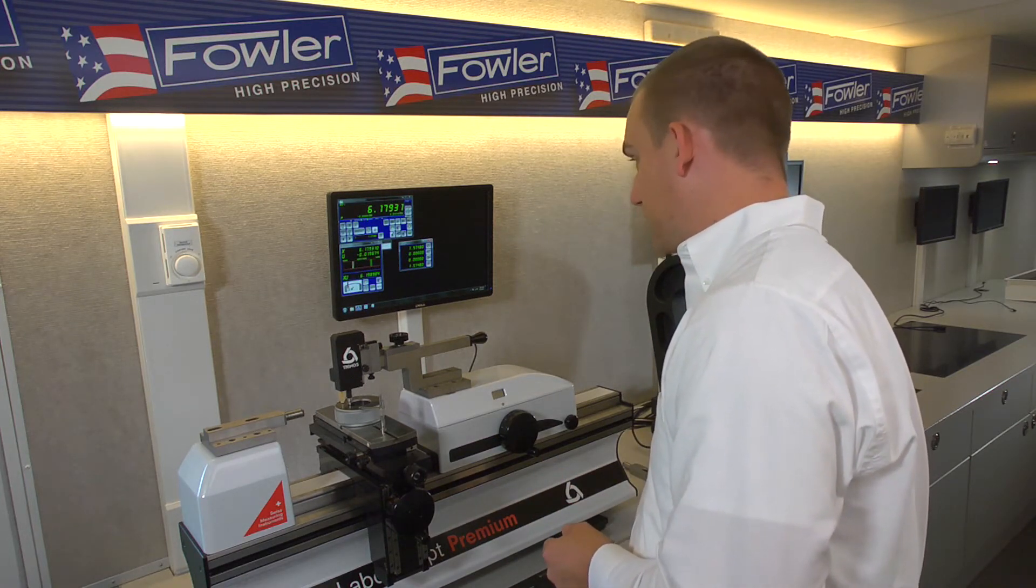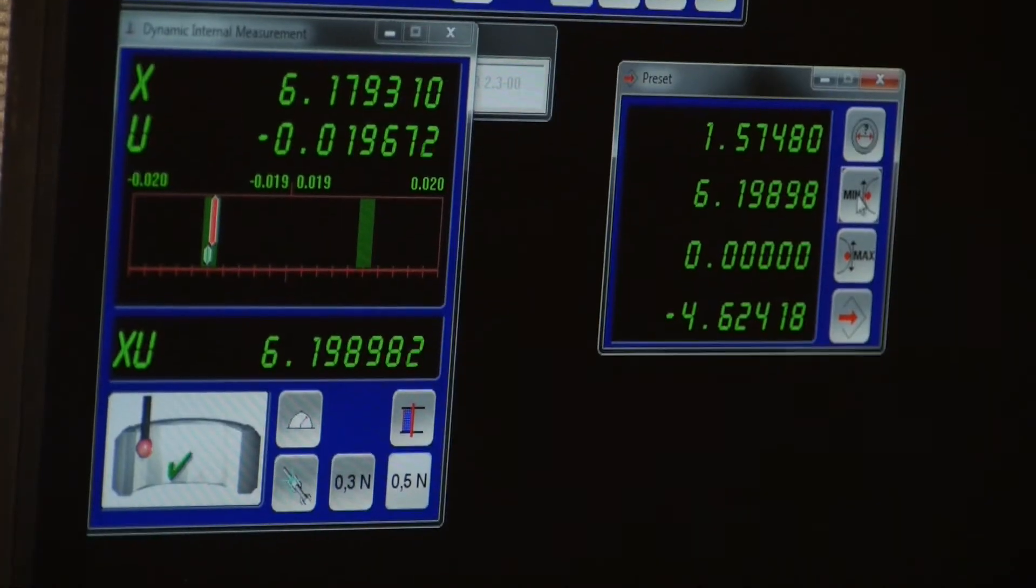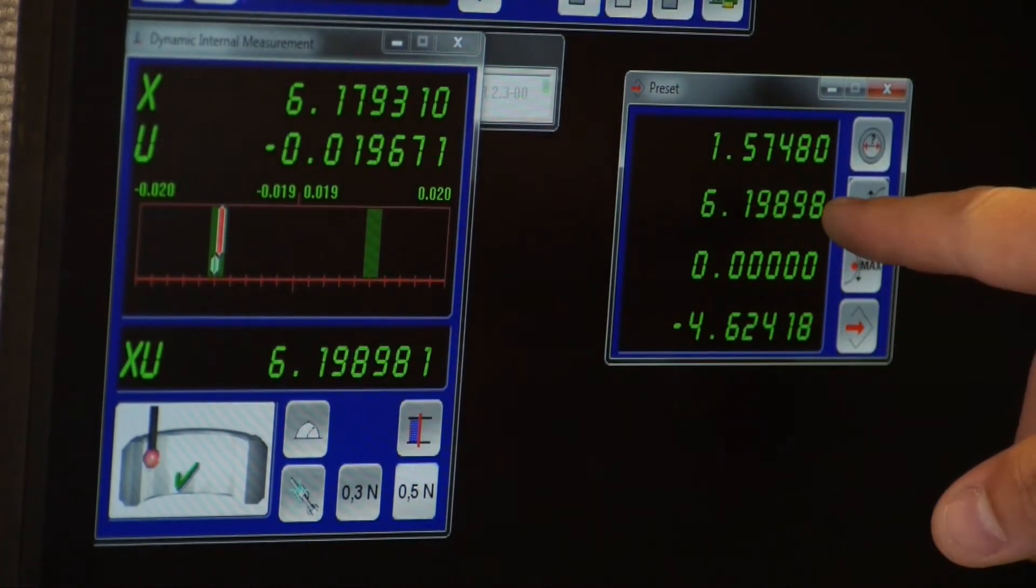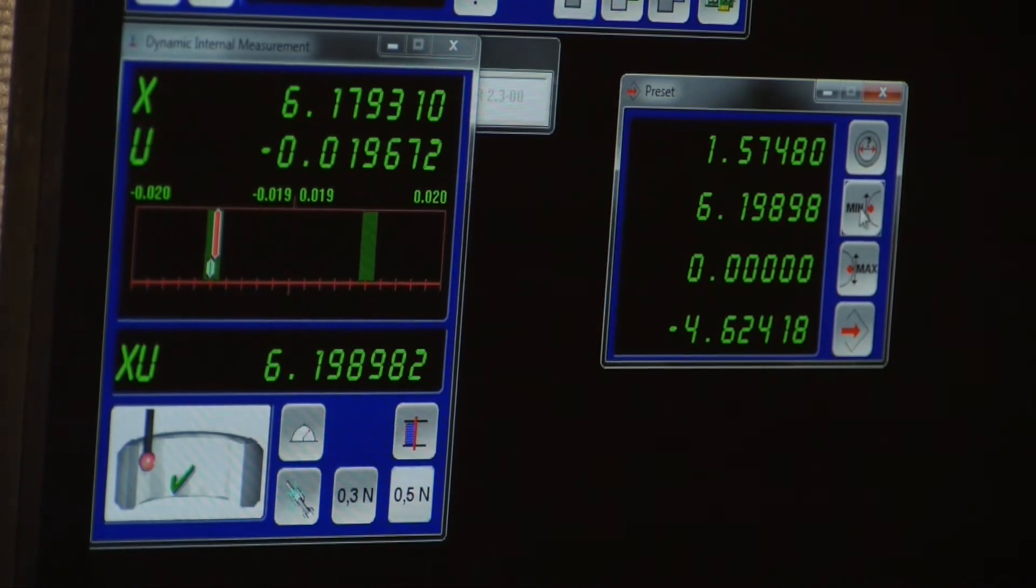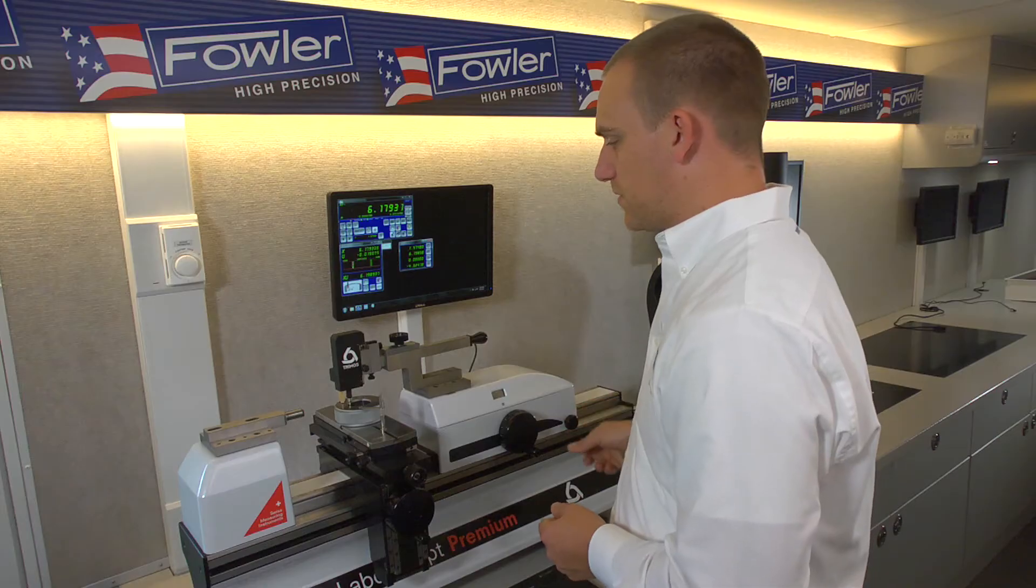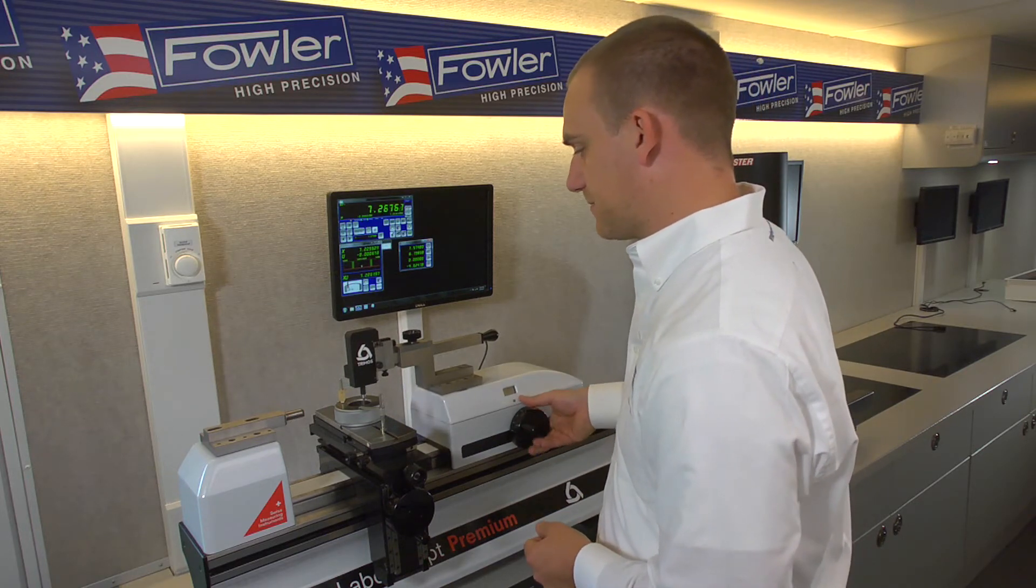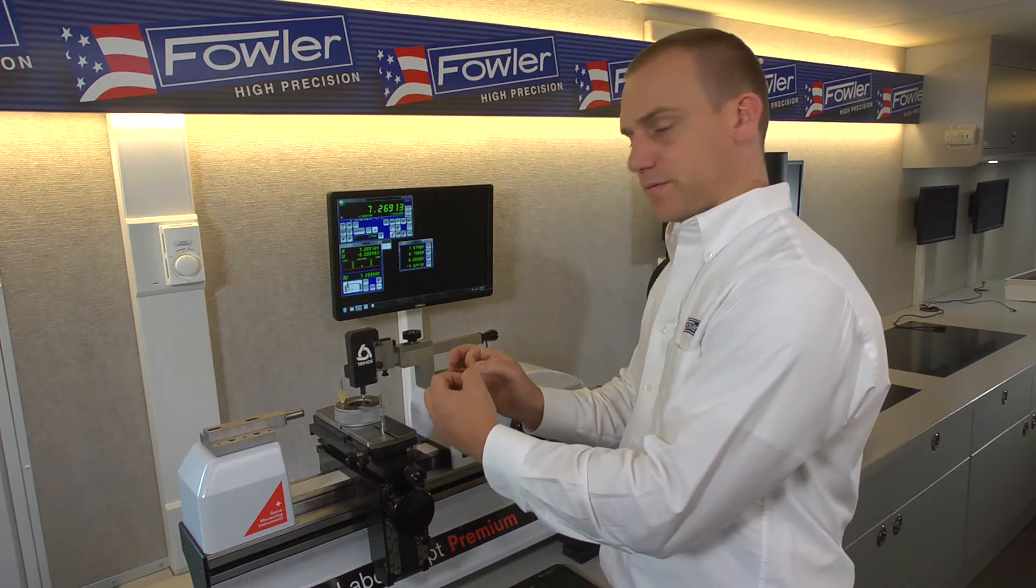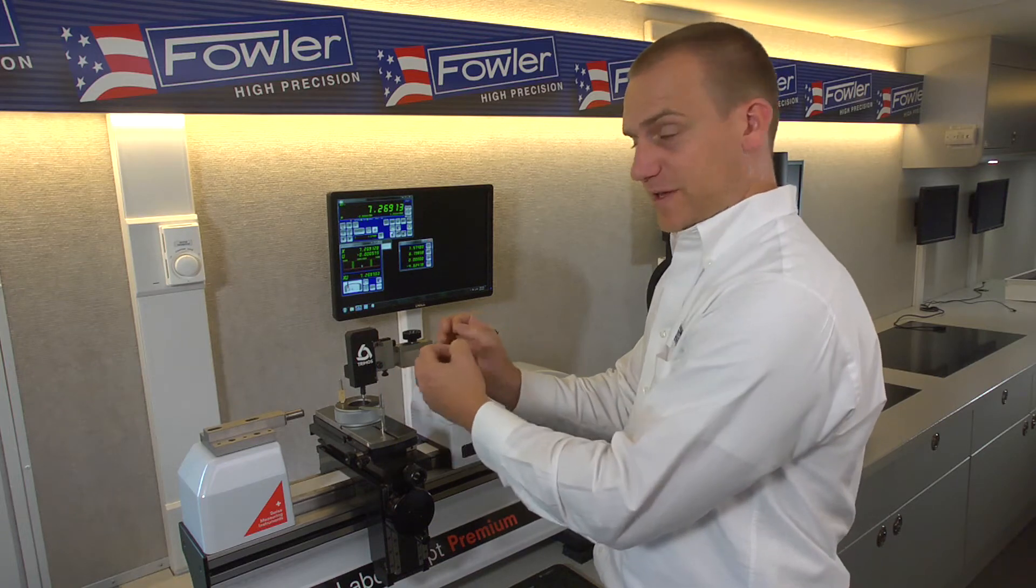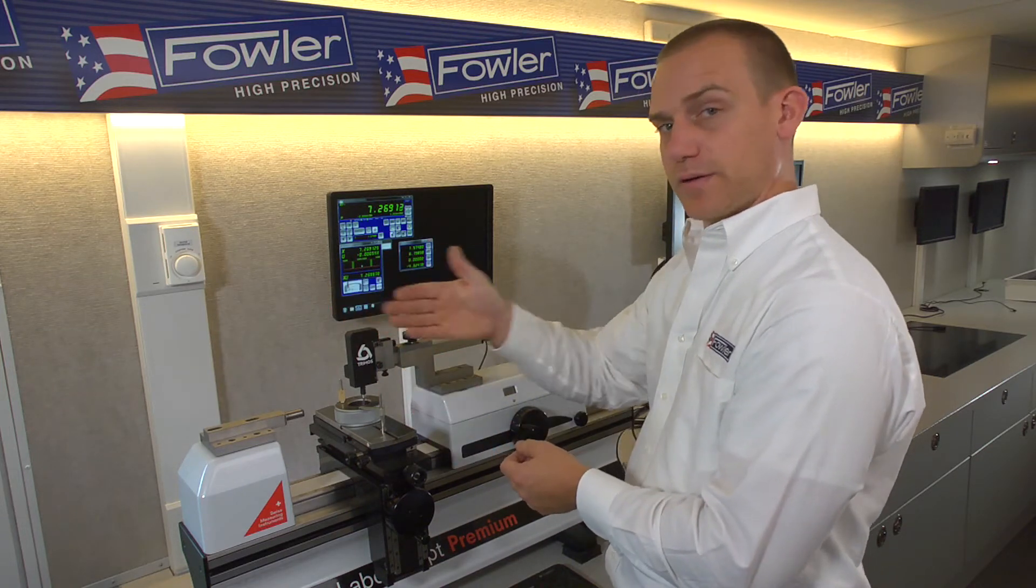We'll use the next row down on the wizard here, use the min. So that takes our current XU position and drops it there. Since this is a single ball probe, we don't have to do a sweep on the right side. A two ball probe, we can't guarantee that it's perfectly in line. So it's good practice to sweep on both sides.